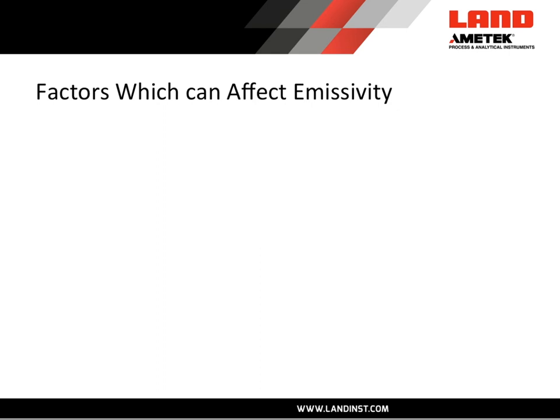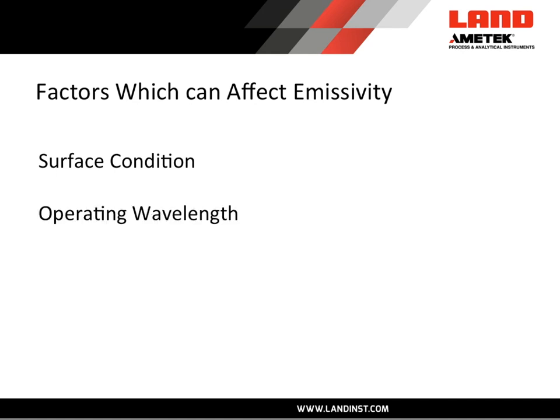So what are some factors which can affect the emissivity of an object? We've already seen that something unoxidized versus very oxidized can have a different emissivity value — that's surface condition. Also the operating wavelength will affect emissivity values on some materials. The viewing angle to the surface matters, and also the temperature of the material — if it's extremely high and starts to glow, the emissivity value will tend to rise.